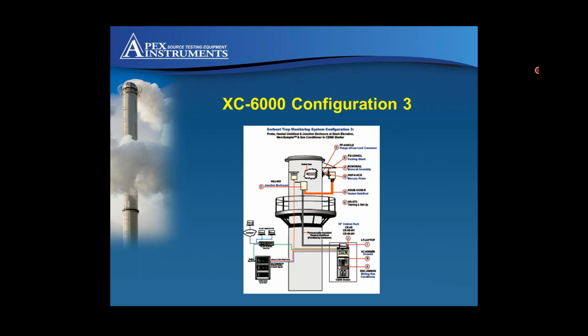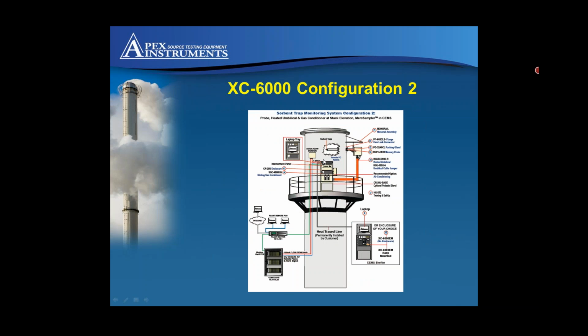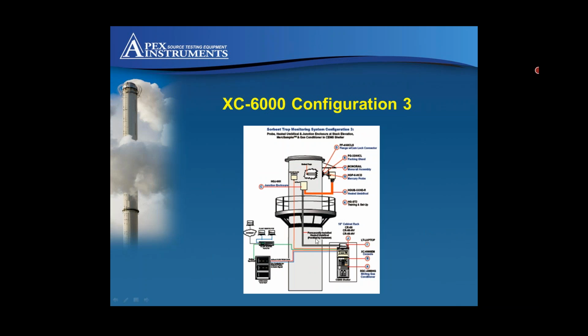When you do configuration 2 or 3, is that dilution to get that sample down, or is that 100%? 100%, just a regular, permanently installed heated sample line is what we need. The big difference between configuration 2 and 3 is the permanent sample line going from the platform down to the CEMS shelter. Configuration 2, it just has to be a freeze protect line. Configuration 3, you're bringing all the signals, heater controls, etc., up through a heated sample line, which has to be kept up around the 250 mark.